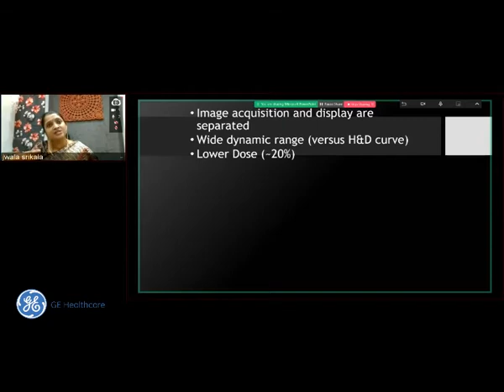It has a wide dynamic range. What does it mean? If my tech didn't have the best technique, she didn't use the most ideal kV, the latitude was much, much more forgiving, in the sense I could do a lot of post-processing to a not so perfect technique and still get diagnostic quality images. It required a little bit lesser dose than screen film mammography, but the limits were the same as film screen mammography. Slightly higher kVp was required.